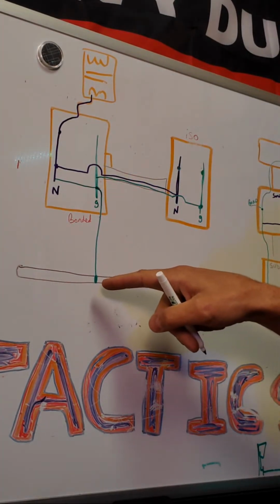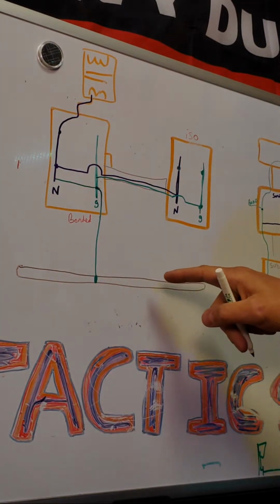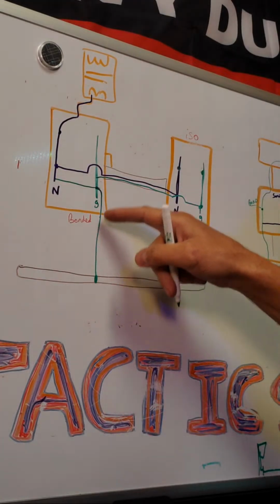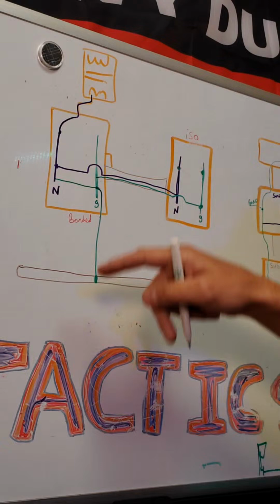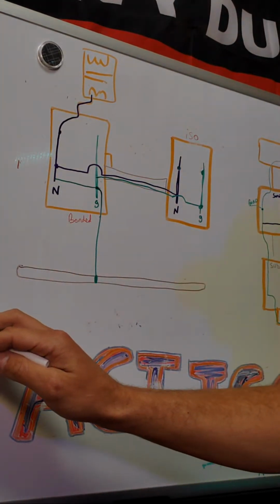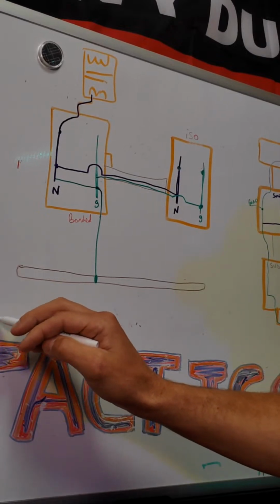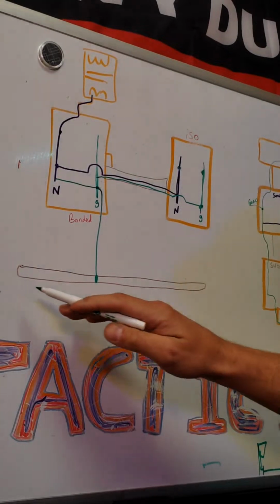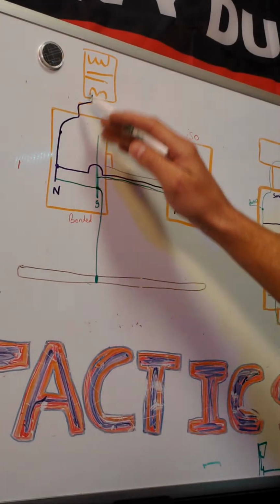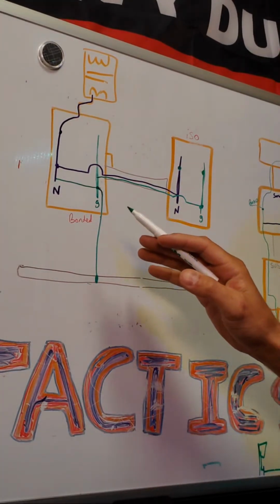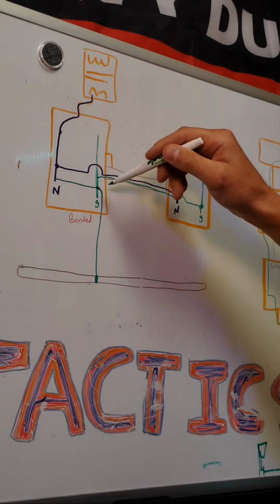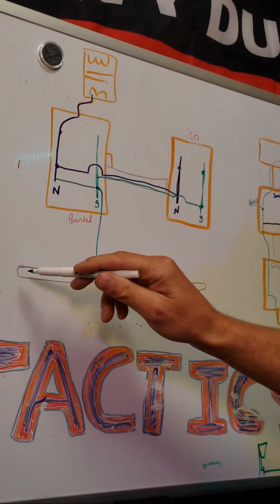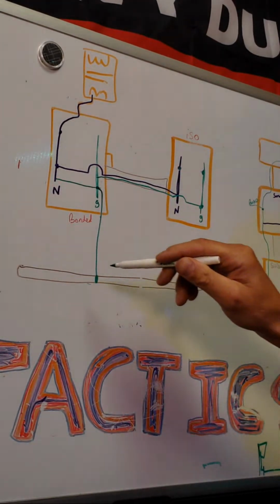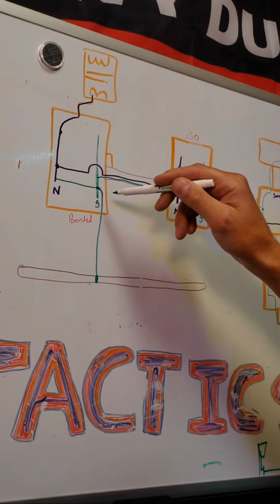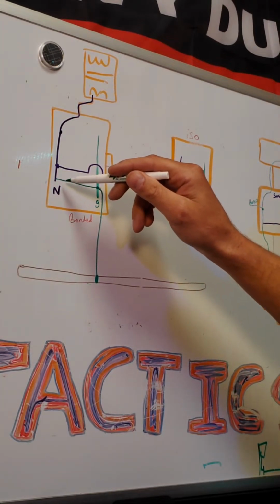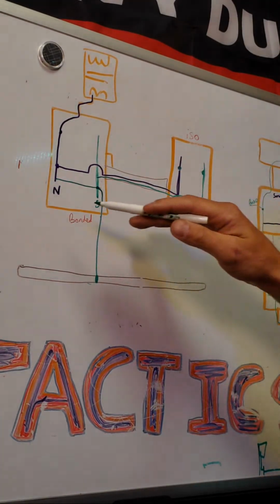So what we're doing is, if it's likely to become energized, if it's metal pipe, things like that, if current gets on it, we can get the current off of it to get back to the source. If we got a gradient voltage where there's voltage coming in this direction, right? We've got a means to grab it and put it kind of back to the source. We can dissipate current. It's great for lightning strikes because we can get any of that current back to the earth where it came from. But grounding electrodes don't really do anything else for us. What trips the breaker is the ground tied to the neutral at the source. And you want to limit how many times you bond for this reason.